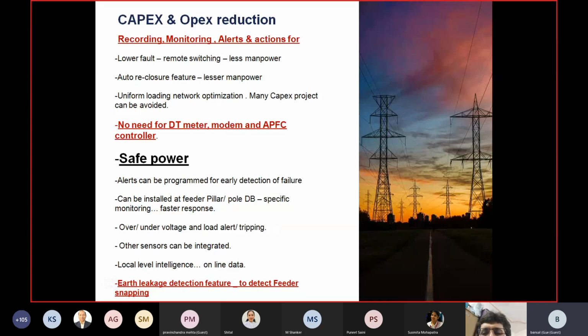And then we said, no more augmentation, no more new installation. If you have an overloaded transformer, look for one nearby that's underloaded and transfer the load. No more adding of assets. Have more feeders, no issue, but no more distribution transformers. And that has worked. In the last 2-3 years, the capex cost has gone down drastically because of that, and there are more feeders.